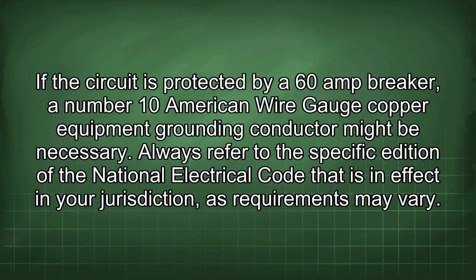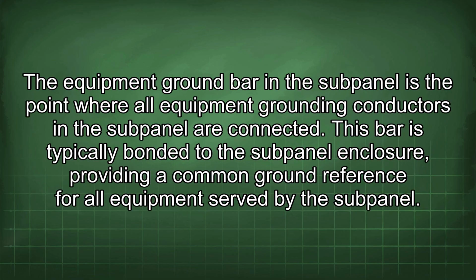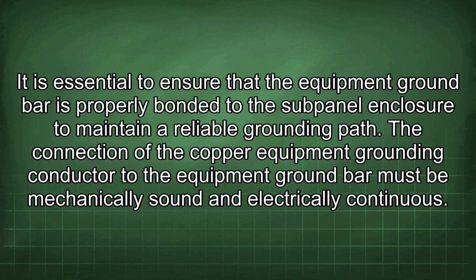If the circuit is protected by a 60 amp breaker, a number 10 American wire gauge copper equipment grounding conductor might be necessary. Always refer to the specific edition of the National Electrical Code that is in effect in your jurisdiction, as requirements may vary. The equipment ground bar in the subpanel is the point where all equipment grounding conductors in the subpanel are connected. This bar is typically bonded to the subpanel enclosure, providing a common ground reference for all equipment served by the subpanel.